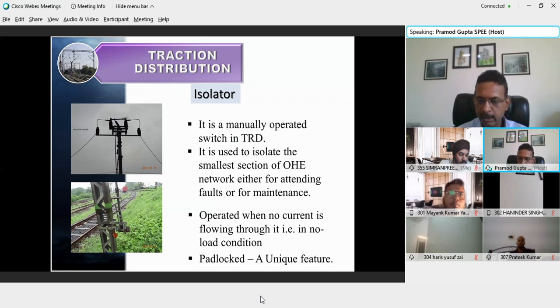Now the role of the padlock comes in. The lever is very easy to operate. Once I operate it by 180 degrees, I am supposed to lock it in position so that nobody else can operate it again accidentally without knowing that some maintenance activity is being carried out. Maintenance staff are actually touching the contact wire or attending fittings provided in OHE. Some accidents have taken place in the past where the lever was operated in the normal position and the maintenance staff were electrocuted. So it is the responsibility of the OHE maintenance staff to ensure this basic principle, and it is already laid down in the work instructions issued to TRD staff.